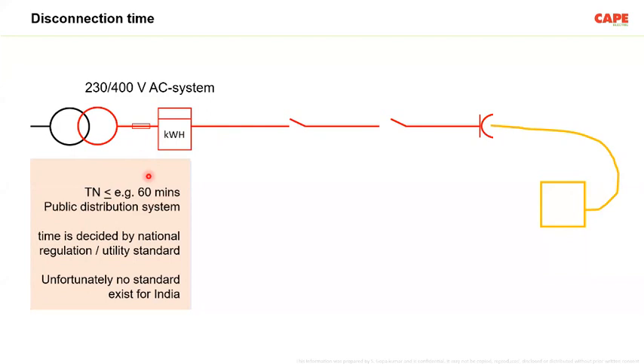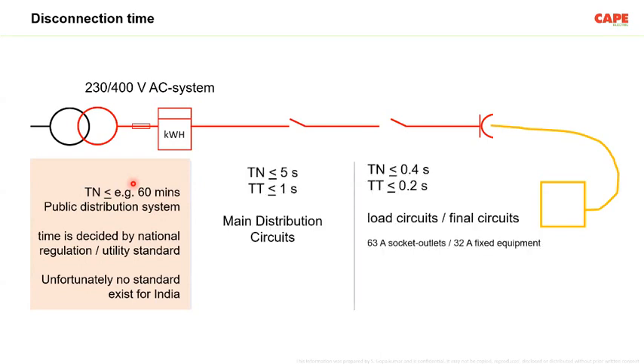Most nations have made regulations and fixed this disconnection time. For example, in a TN system, the maximum is 60 minutes. Within 1 hour, in case of any fault, the HT supply must be disconnected, and such regulations are made and followed. Whereas in India, unfortunately, this is not very much followed. As a result, a lot of accidents are happening. So please understand that in case of fault, you cannot leave the circuit under faulty condition for a longer time.